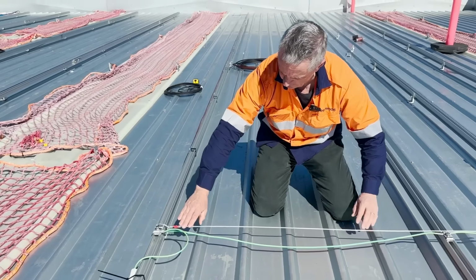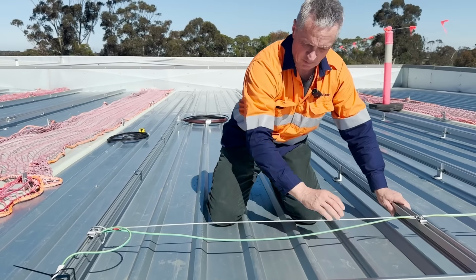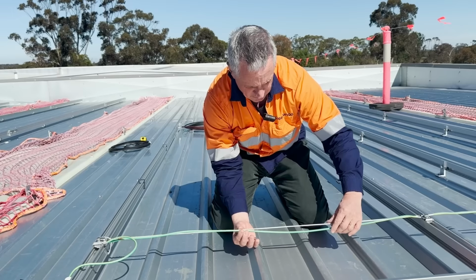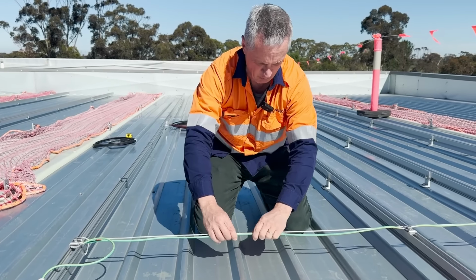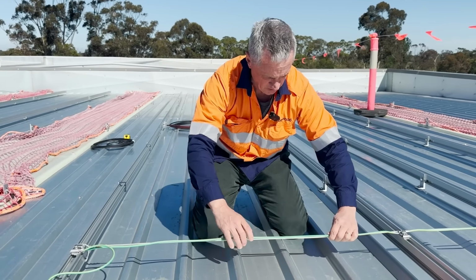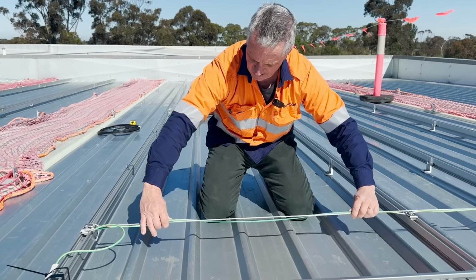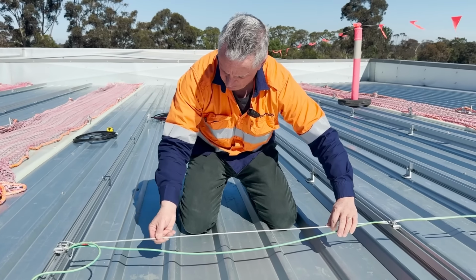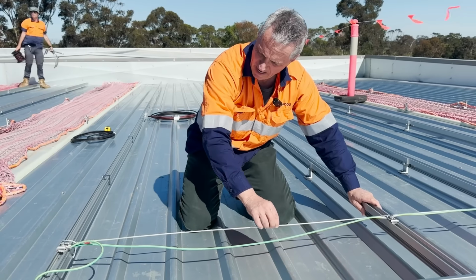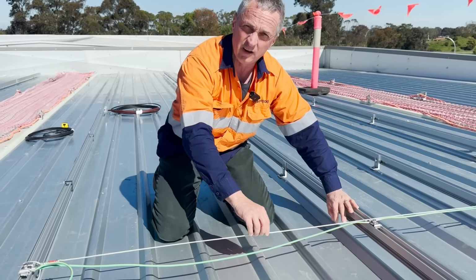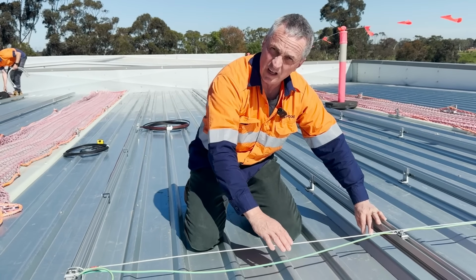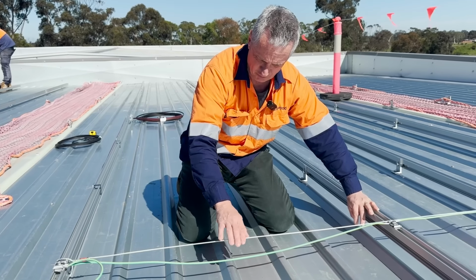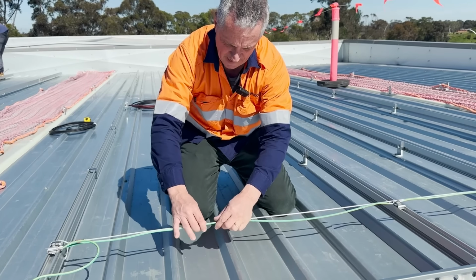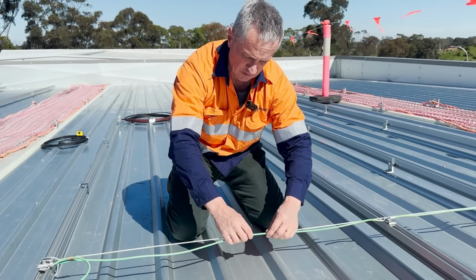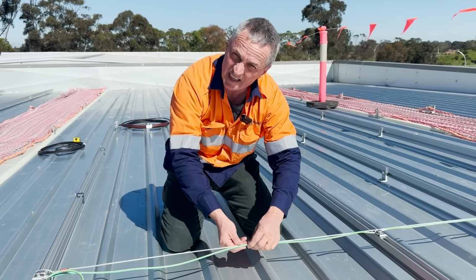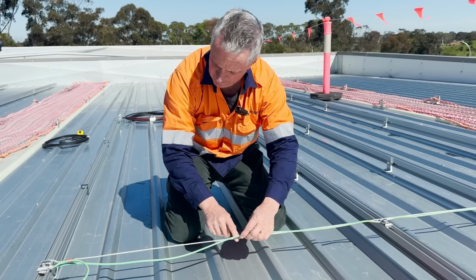Look at the catenary wire. You can see this catenary wire, effectively it's structural. It's designed to keep the cabling, in this case earth, but a lot of catenary wires will carry both the earth and the DC cable, and they'll be clipped here, here and here using a stainless steel cable tie. This particular catenary wire is quite heavy duty, stainless steel, but it's also got a plastic covering, so it's a little bit easier to handle. You're not going to get any issues with braids coming and scratching, creating puncture wounds, or issues with the cable rubbing against the actual catenary. Because it's very, very smooth, right?